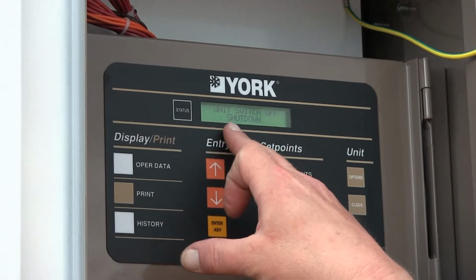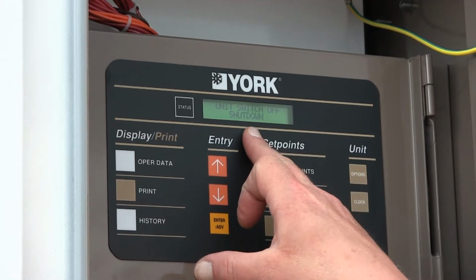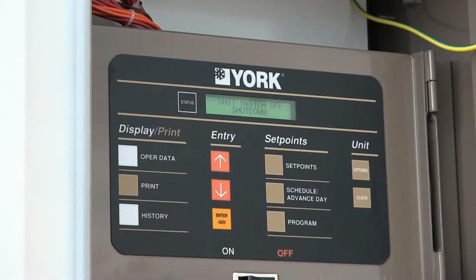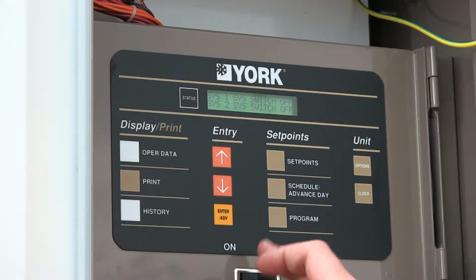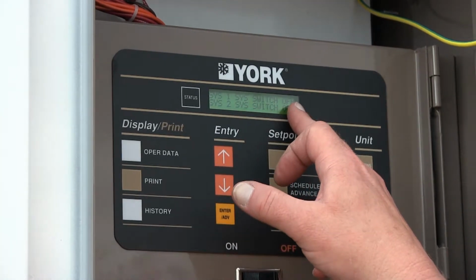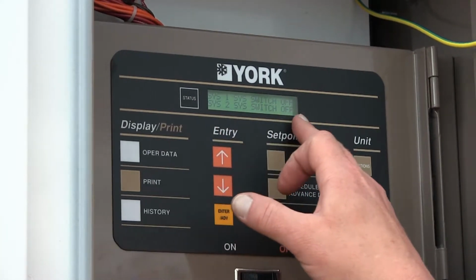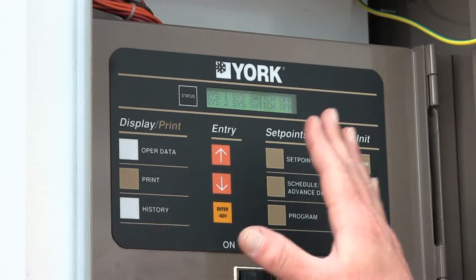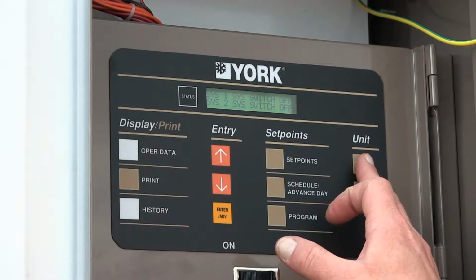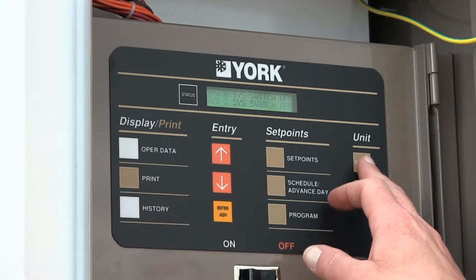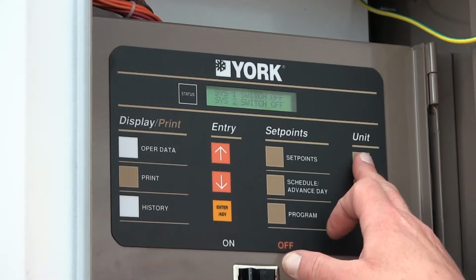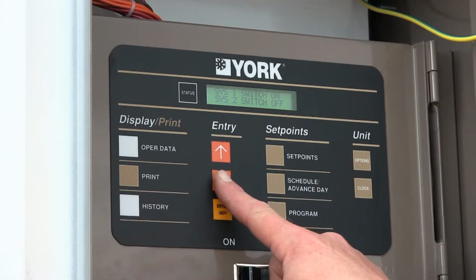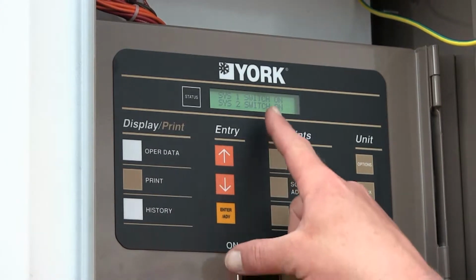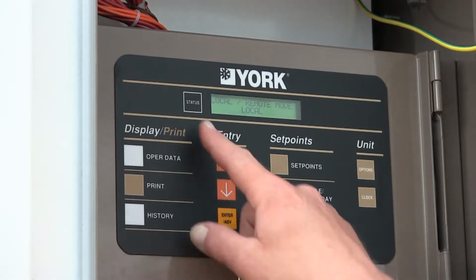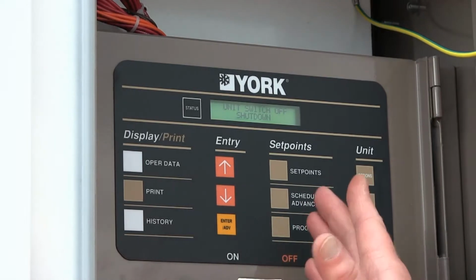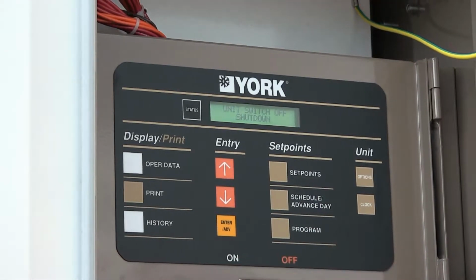And currently it says unit switch off, shutdown. It's referring to this unit switch here. So if I turn it on, you'll see that it says system switch is off for circuit 1, system switch is off for circuit 2. That's actually a software switch. It's located under the options key. So we'll turn this back off. We'll go into the options key, push it twice, and we're going to turn both of the systems on. Now they're both on, and we're going to push enter. And go back to the status. Now it says it's back off on a unit system switch right here.